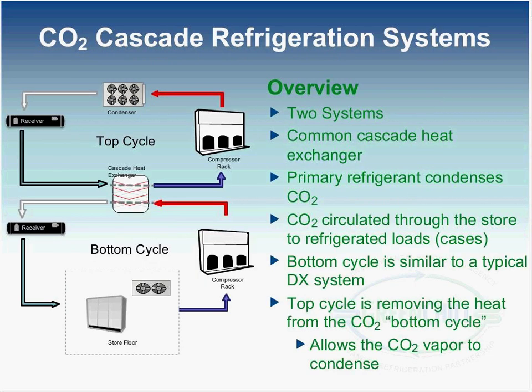If you take a look at a cascade system, there's definitely a variation on that in that they're really dependent systems. Each of these sides really operate almost the same way as a direct expansion system would that we talked about earlier. Basically, what you're going to have here is what we refer to as a top cycle and a bottom cycle. The primary purpose of the top cycle is simply to condense the CO2 that is found in the bottom cycle. The CO2 in the bottom cycle is then circulated to the store, where there are the refrigerant loads, and then it comes back around, and once again, that refrigerant is condensed at the juncture of the top cycle and bottom cycle. Those two cycles are connected through a heat exchanger, which allows that to take place.